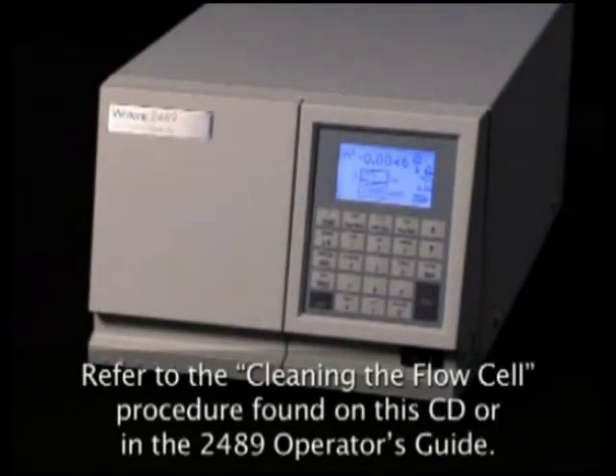Before performing this procedure, you should flush and dry the flow cell by following the Cleaning the Flow Cell procedure on this CD or refer to the 2489 Operator's Manual.